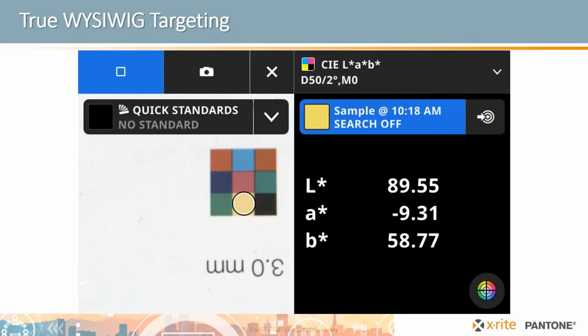So how does it work? Well, I mentioned that there's an LED light source, and part of that is the measuring light source, but there's also a light that comes on in the device when you get ready to measure, and that light stays on so that you can validate your measurement area. Then when you go to measure, that positioning light goes off, and you have your LED that actually captures the spectral data.